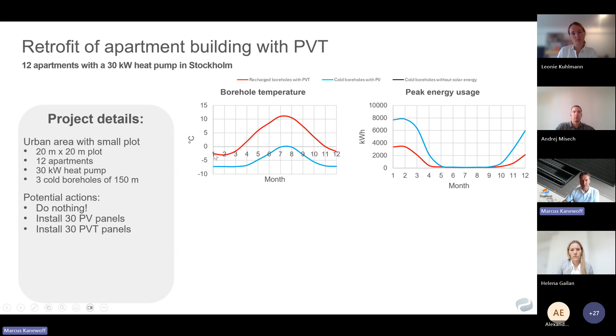With recharge, we could come to this situation and have the heat pump in operation with good performance throughout the year. The peak energy usage fell from 8,000 kilowatt hour per month down to 3,700. The system performance factor was 2.2, which is quite low for a geothermal heat pump. But that could be raised to 3.7 with recharge, just to have the normal good conditions in the boreholes. And then again, it's a very good solution for heating and hot tap water, 3.7.